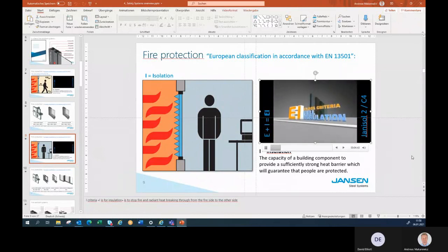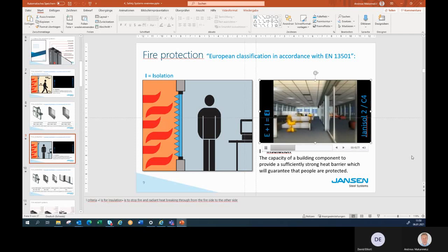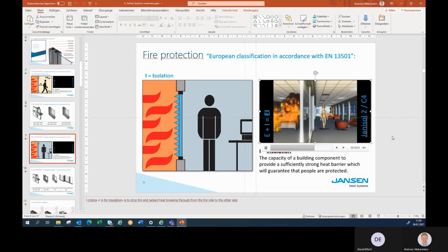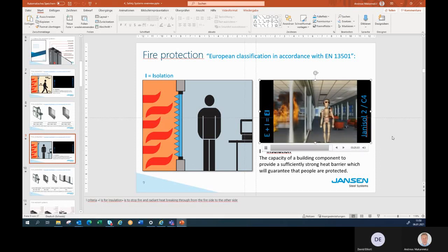EI-class, full insulation. These are high-end products that can actually act as a barrier to radiant heat, restricting the heat to less than 1 kilowatt per square meter at 1 meter distance. You can stand near the glass on the non-fire side and not feel the heat.